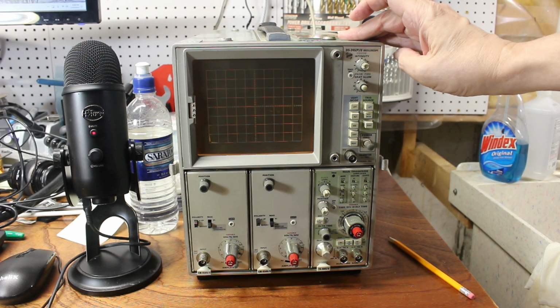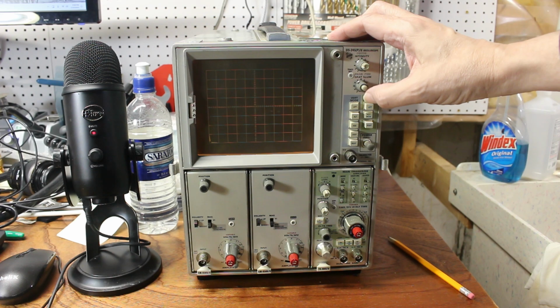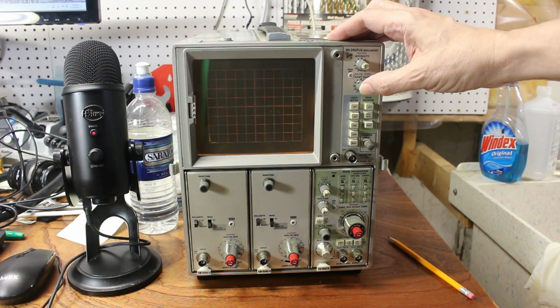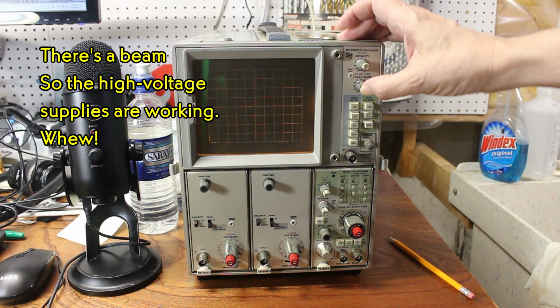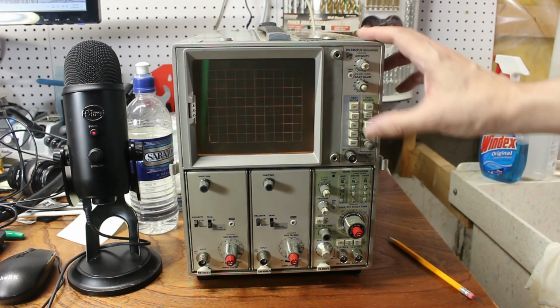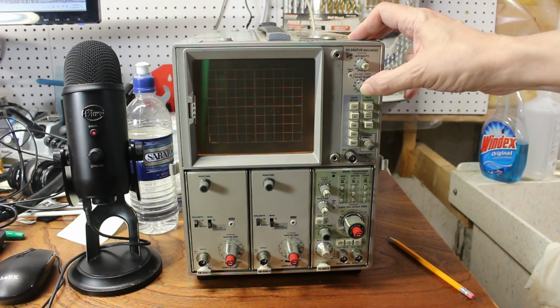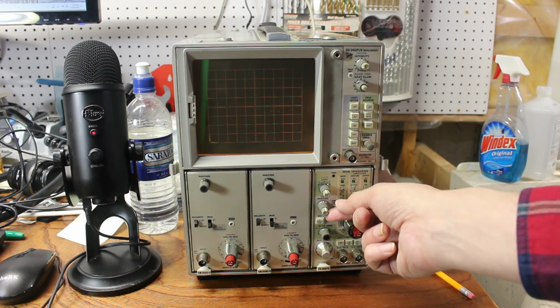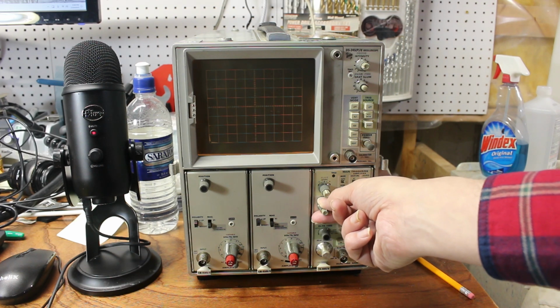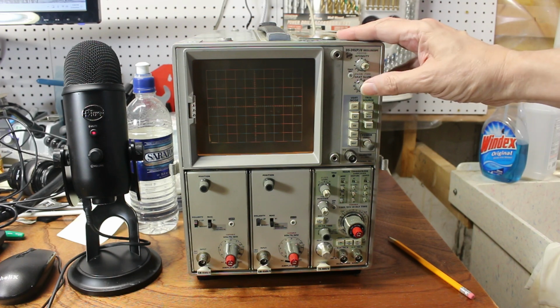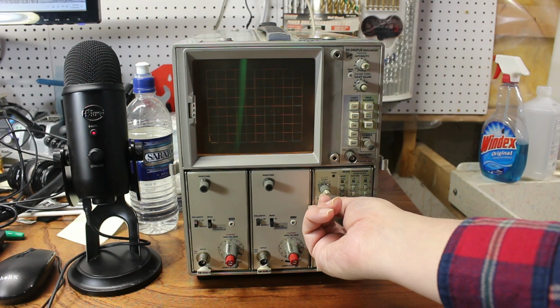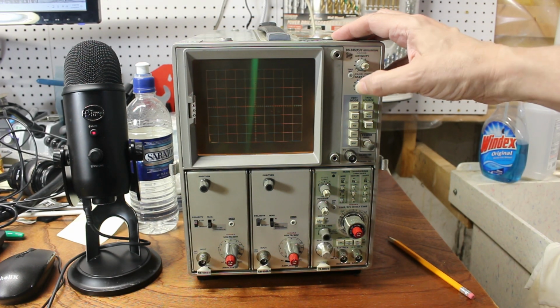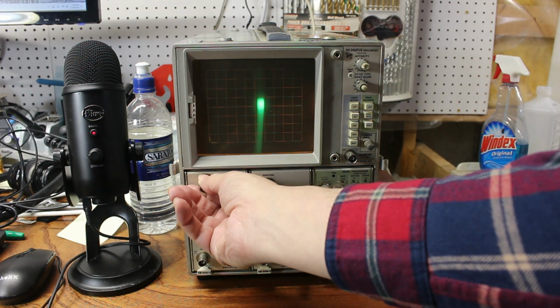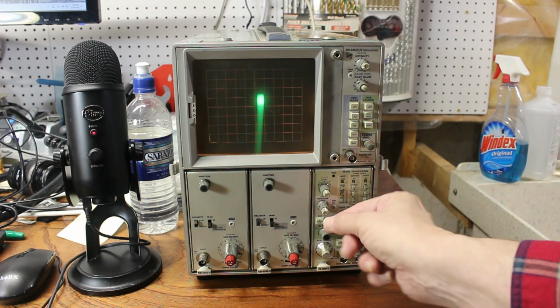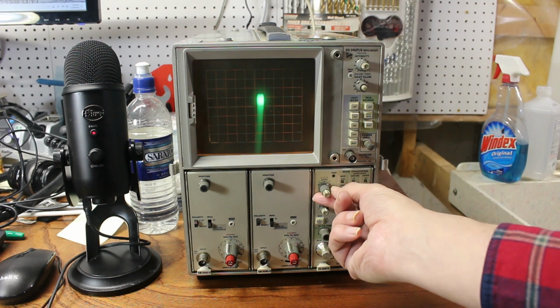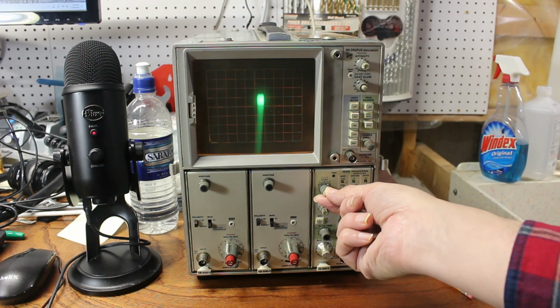Graticule lights up. And I remember the thing always took a while to warm up. But I should be seeing the beam by now. It's there somewhere. Not in the greatest focus. And it's way off to the left and way off at the top. So let me see if I can bring down the vertical position some. Oh wait, that's the horizontal. I'm sorry. Bring the horizontal position down some. Well, I can get it approximately centered. And adjust the vertical position, and there it is. It's trigger level and slope.